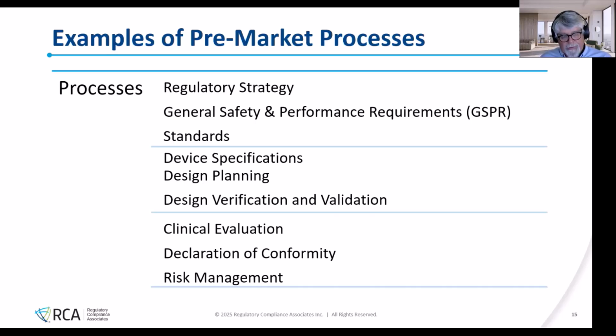Clinical evaluation, this is huge. And sometimes we think that all devices require a clinical investigation or clinical trial. That's not the case. Not all devices require a clinical investigation and clinical trial, which can be very time-consuming and expensive, but all devices require a clinical evaluation. And importantly enough, this clinical evaluation has to be updated as your product matures through its product life cycle. So you could have clinical evaluation Rev A, then B, then C, then D as you progress, and you tend to tell us how often you're going to evaluate that. Clearly, you want to standardize, maybe in a 2-year cycle unless something happens in the market, okay?